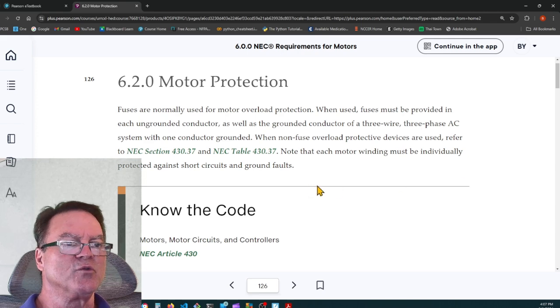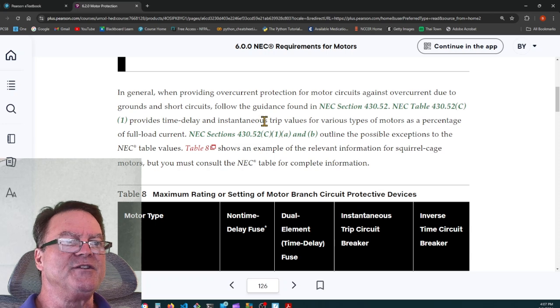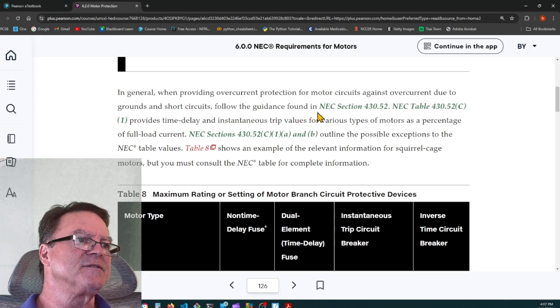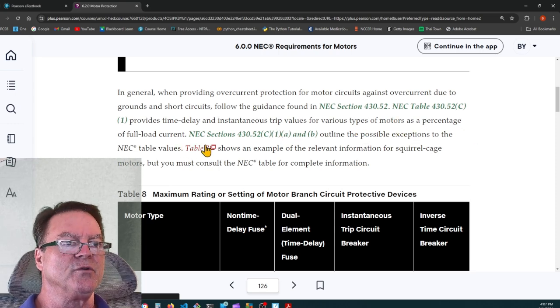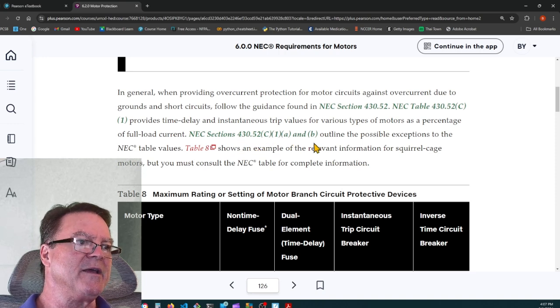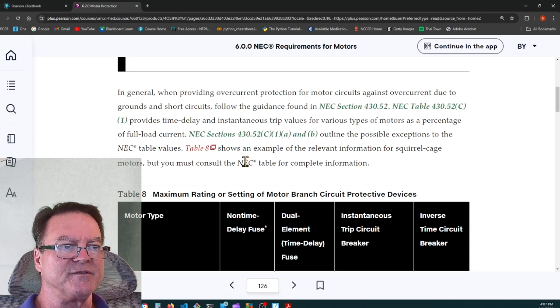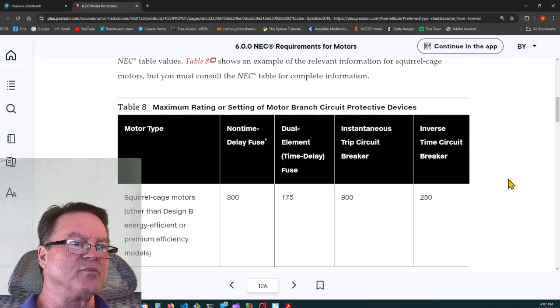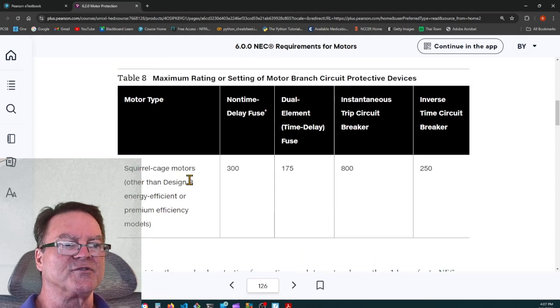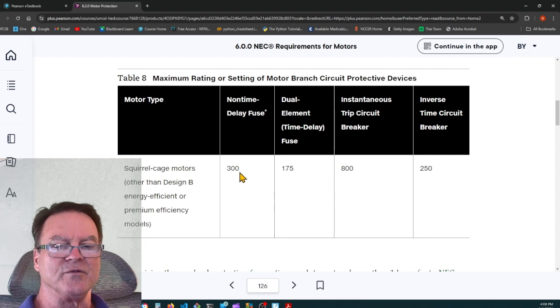Note that each motor winding must be individually protected against short circuits and ground faults. In general, when providing overcurrent protection for motor circuits against overcurrent due to grounds and short circuits, follow the guidance found in NEC section 430.52, NEC table 430.52(C). It provides time delay and instantaneous trip values for various types of motors as a percentage of full load current. NEC section 430.52(C)(1) and exceptions outline the possible exceptions to the NEC table values. Table 8 shows an example of relevant information for squirrel cage motors, but you must consult the NEC table for complete information. So here it's saying that if you have a squirrel cage motor other than design B, energy efficient or premium efficiency models, for non-time delay fuses, you're going to have 300% of the running current in those tables.